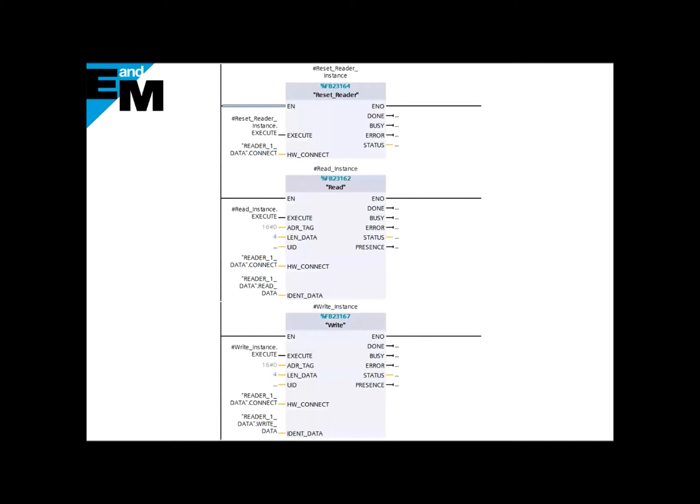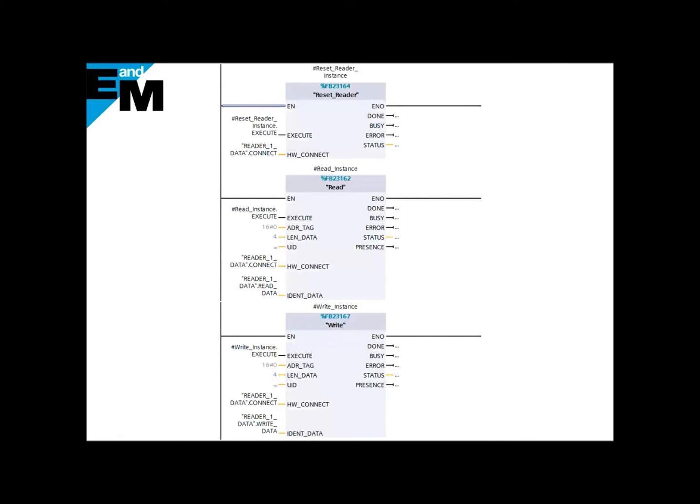What makes it even more unique is that the RFID programming is done in ladder logic within TIA Portal, and the RFID blocks can be downloaded from Siemens support site. For a simple RFID project, all you need to do is parameterize three blocks: one for resetting the reader, second one for reading data, and the third one to write data. All complex programming is taken care of in the background for you.